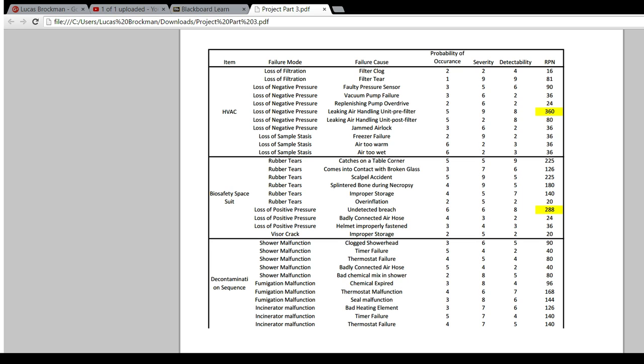Another big issue is the HEPA filters that filter all of the microbes out of the air in a biosafety laboratory. Looking at these filters, one could become clogged, and there are sensors. Basically, it's a pressure differential sensor across the filter that indicates whether it's working or not. And a clog is very detectable; it has a severity of 2 because its detectability is 4. Basically, all that means is that microbes wouldn't get out, which is what you're looking for anyway.